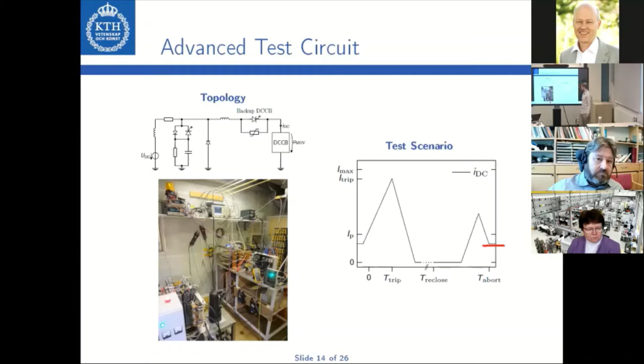Now I want to come to the experimental results. These are mainly taken from publication 7, which is our latest publication. Publication 5 was more or less a pre-study. Here you can see our first test, which was the triggering of the triggered vacuum gap. And this is done for the originally proposed configuration. Initially, the RC circuit is pre-charged from the DC line. The DC sources were then separated from the DC circuit breaker to prohibit that the triggered vacuum gap interacts with the DC sources during this test. The triggered vacuum gap was then manually triggered.